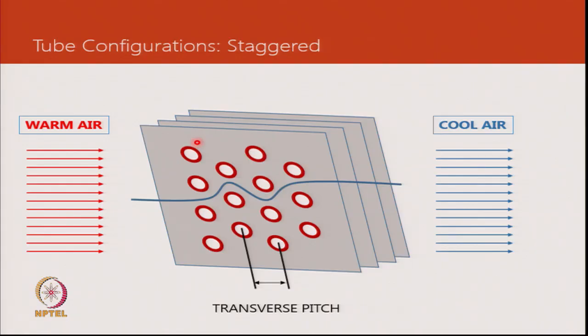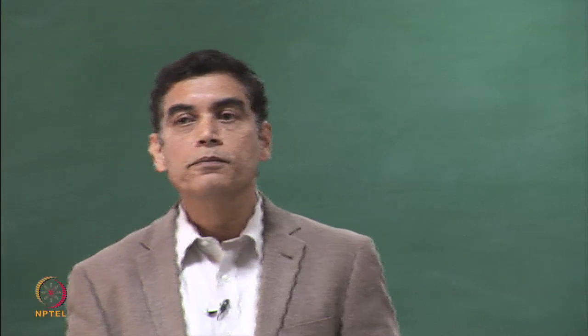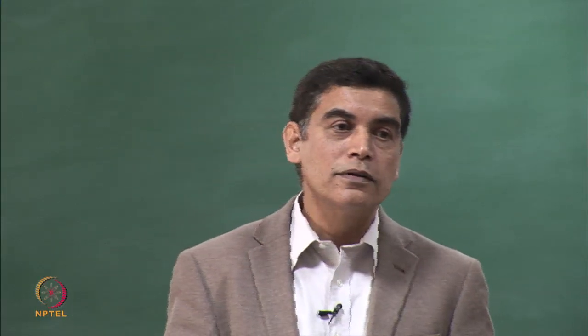To improve heat transfer, a staggered tube configuration is used — instead of tubes being directly in front of each other, they are alternated. This ensures air makes greater contact with the tubes. The penalty for this is increased air-side pressure drop, so air-side pressure drop goes up while heat transfer improves.